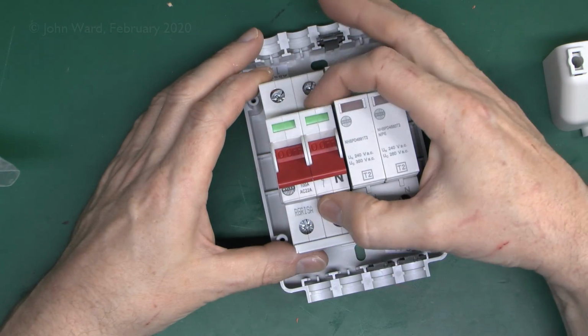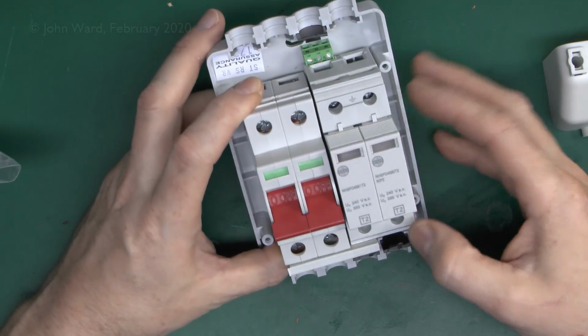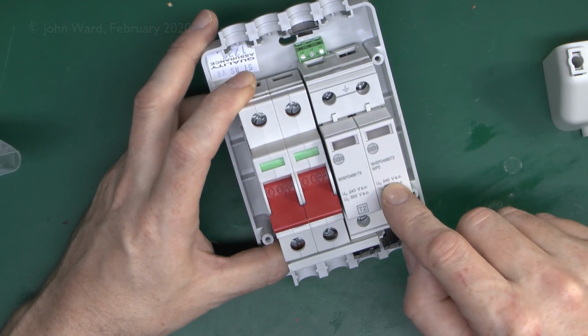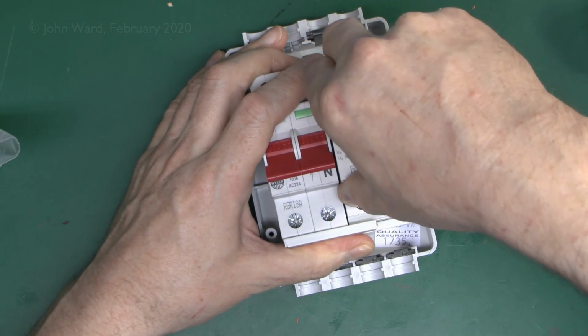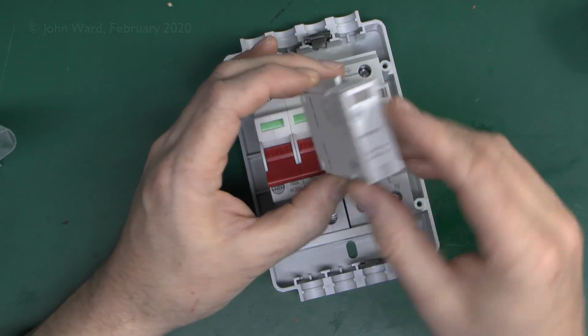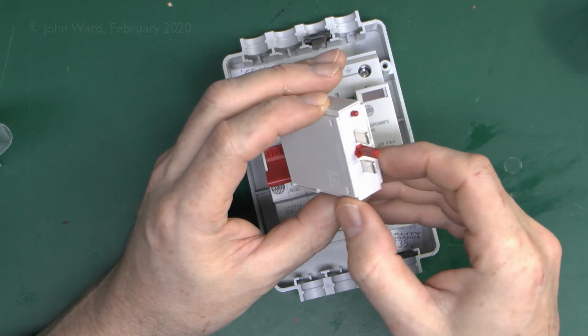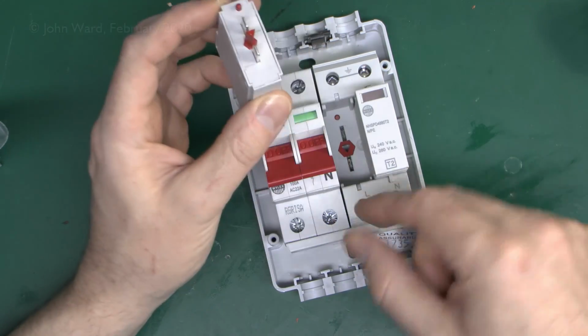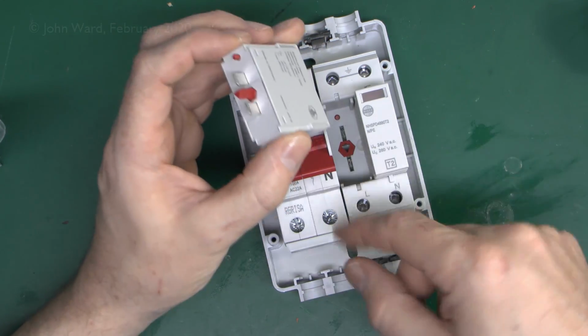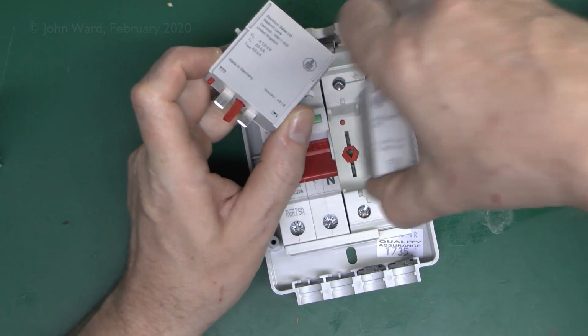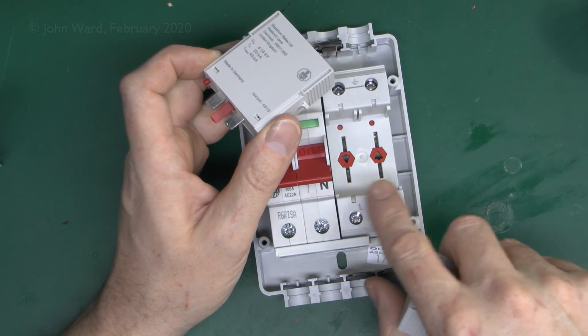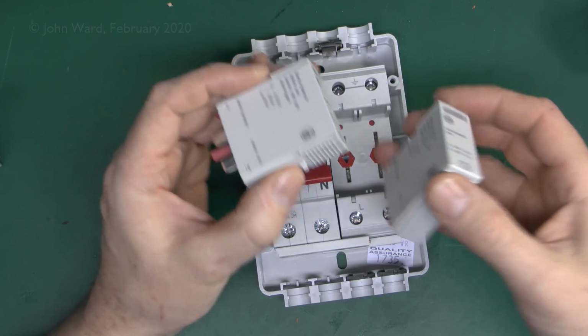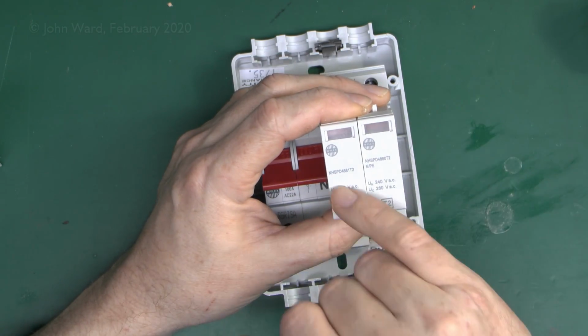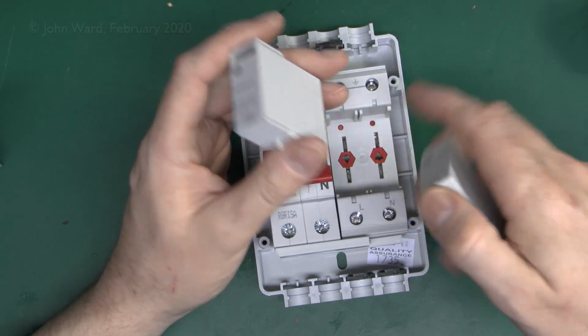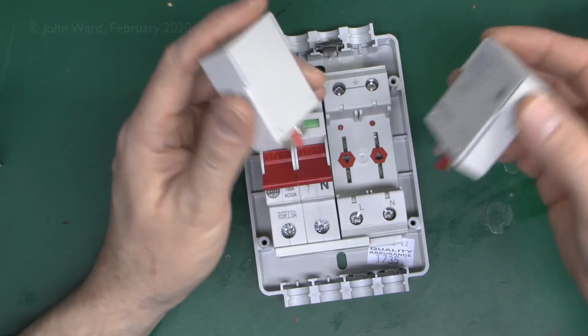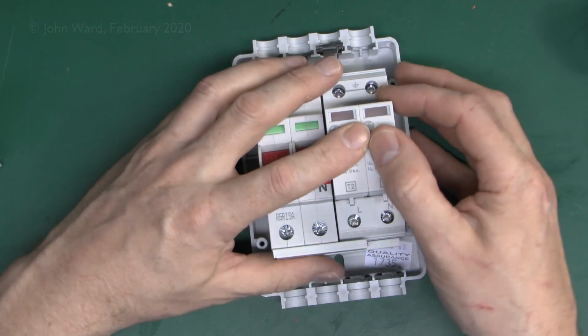It's essentially just the standard 2-pole isolator there, line and neutral, and then we've got the surge protection device over here. And this has the removable cartridges. In this case they're a lot easier to remove, so again it's just the thing there, 2 terminals on the back, and these have a plastic peg here which is basically keyed so it only fits into one of the positions, as the other side, as you can see there, is the other way round, so you can't put the wrong one into the wrong position, as they've made 2 types there. This is the one that goes between the line and earth, and this is the one between the neutral and earth, so those go in like that.